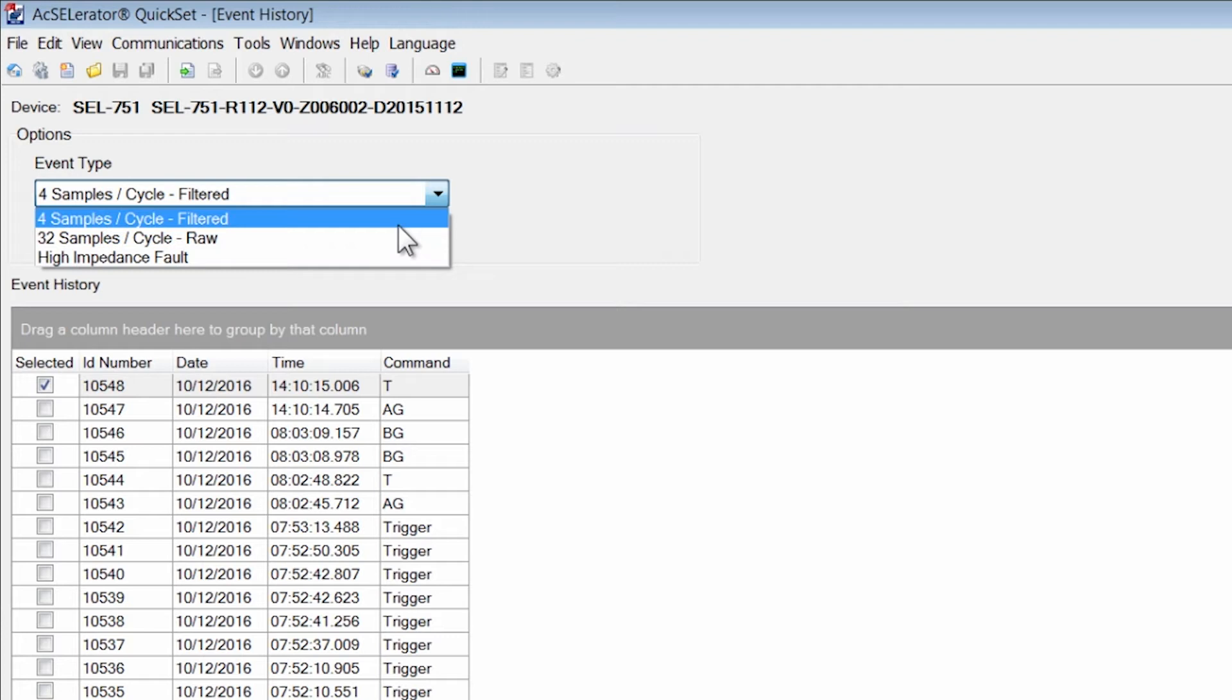The four samples per cycle filtered event gives you the information of whether protection elements operated as they were supposed to. The protection elements in general operate on the 60 Hertz fundamental frequency.